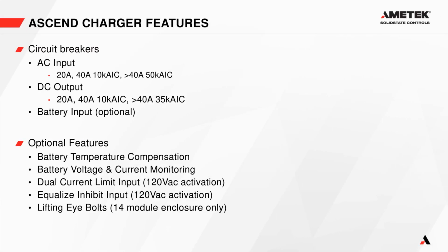For circuit breaker options, on the small 2-module cabinet, we offer 10 kAIC breakers, and on the greater than 40 module or greater than 40 amp current systems, we offer 50 kAIC breakers for the AC input, and the DC output. Same for the small cabinets, 10 kAIC, and for the other cabinets, it's 35 kAIC. And the battery breaker has the same configuration if you choose it in your system.